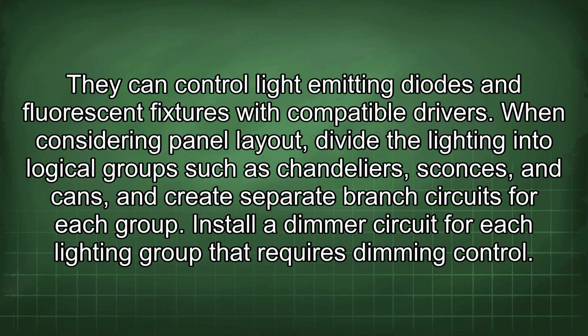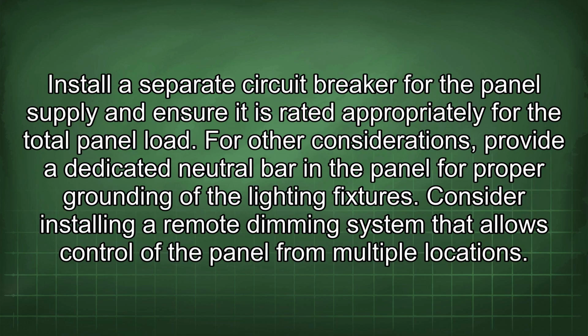When considering panel layout, divide the lighting into logical groups such as chandeliers, sconces, and cans, and create separate branch circuits for each group. Install a dimmer circuit for each lighting group that requires dimming control. Install a separate circuit breaker for the panel supply and ensure it is rated appropriately for the total panel load.